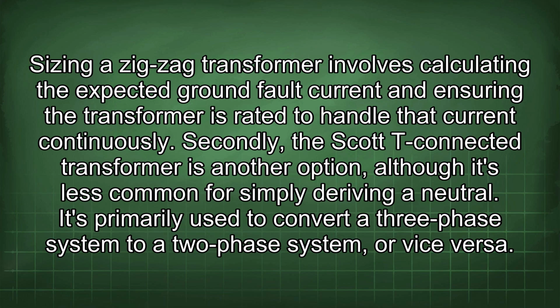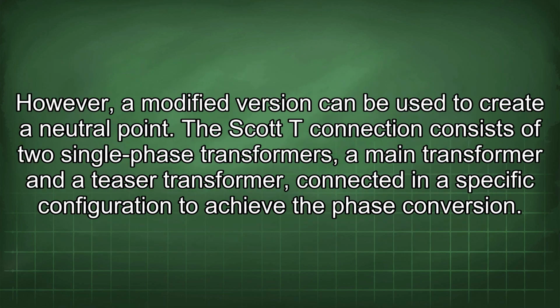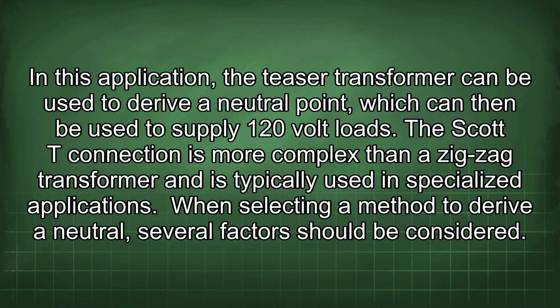Secondly, the Scott T connected transformer is another option, although it's less common for simply deriving a neutral. It's primarily used to convert a three-phase system to a two-phase system, or vice versa. However, a modified version can be used to create a neutral point. The Scott T connection consists of two single-phase transformers, a main transformer and a teaser transformer, connected in a specific configuration to achieve the phase conversion. In this application, the teaser transformer can be used to derive a neutral point, which can then be used to supply 120 volt loads.